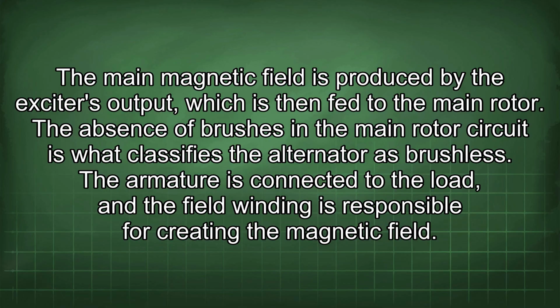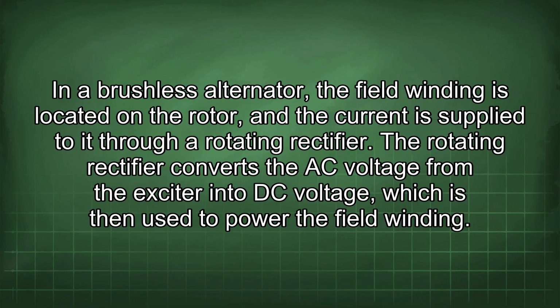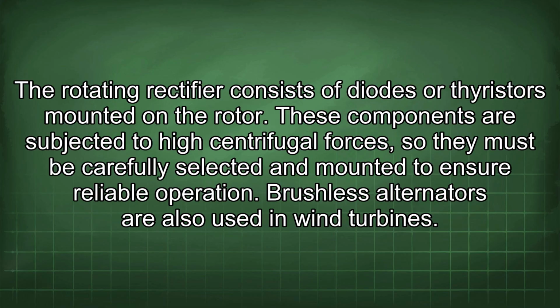The armature is connected to the load, and the field winding is responsible for creating the magnetic field. In a brushless alternator, the field winding is located on the rotor, and the current is supplied to it through a rotating rectifier. The rotating rectifier converts the AC voltage from the exciter into DC voltage, which is then used to power the field winding. The rotating rectifier consists of diodes or thyristors mounted on the rotor. These components are subjected to high centrifugal forces, so they must be carefully selected and mounted to ensure reliable operation.